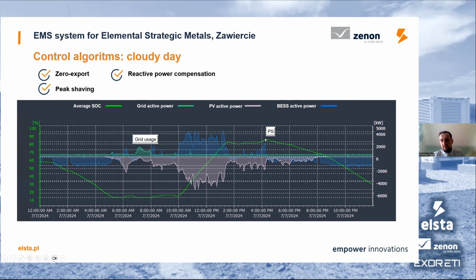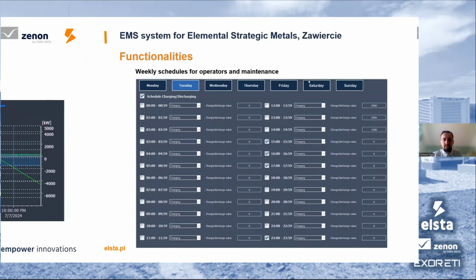So we had energy storage load up to 85%, I would say, and there was not enough power coming from the PV, and there was a peak in the load, which was shaved, as we say, by the energy storage. So you can see that here there was bigger demand on load, low production of PV. So the energy system had to come with help in order to not use the grid.